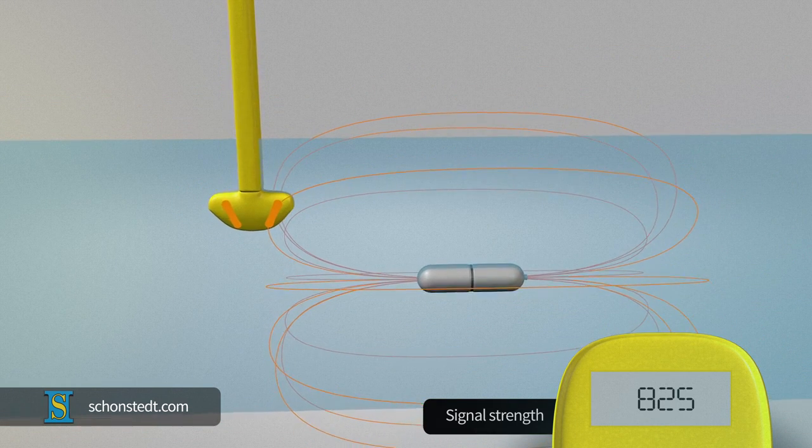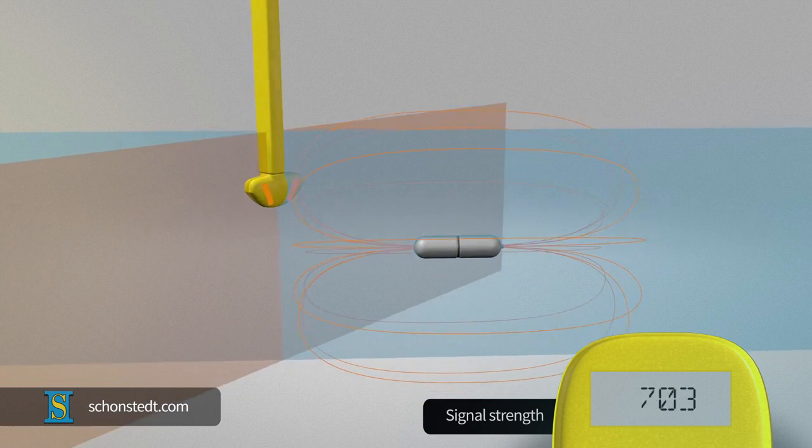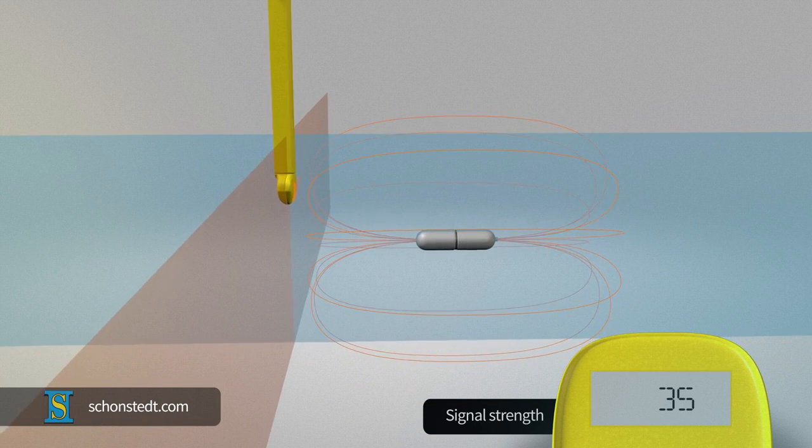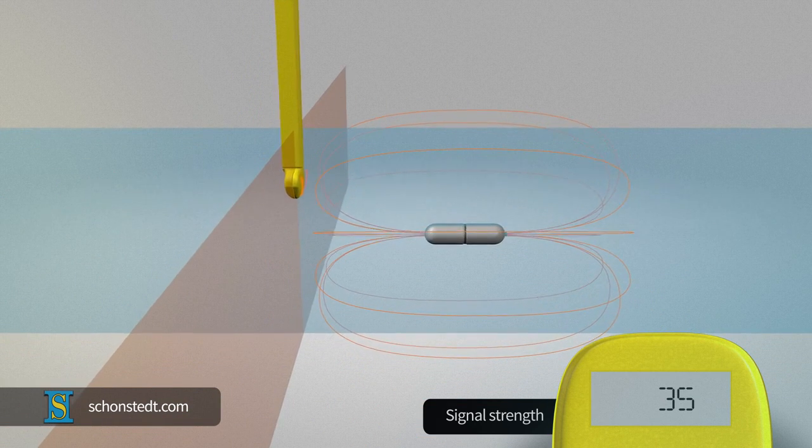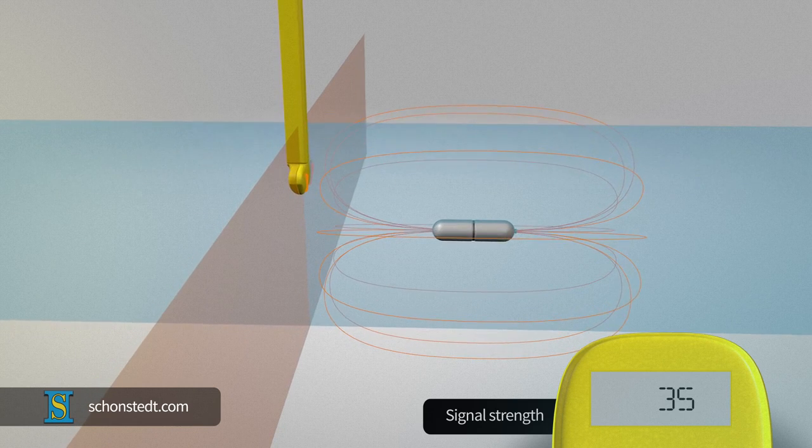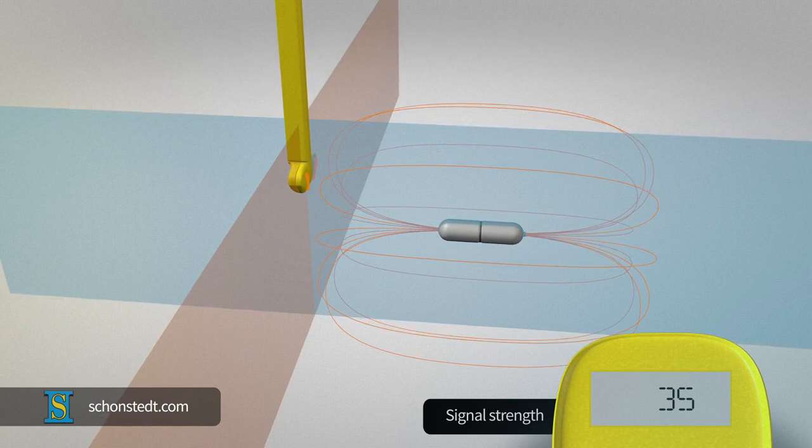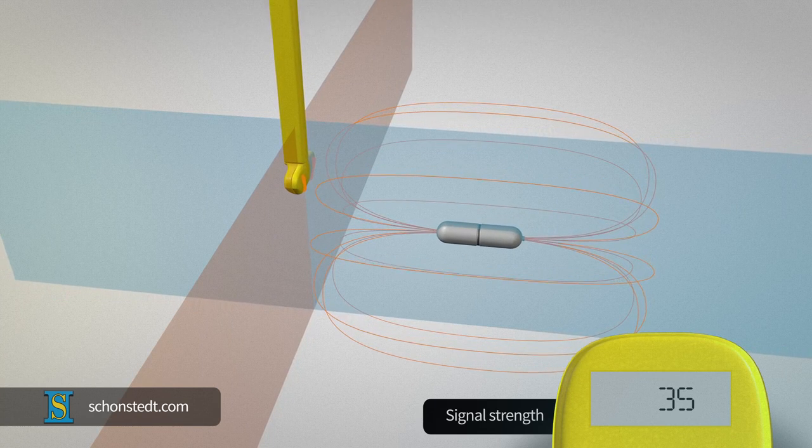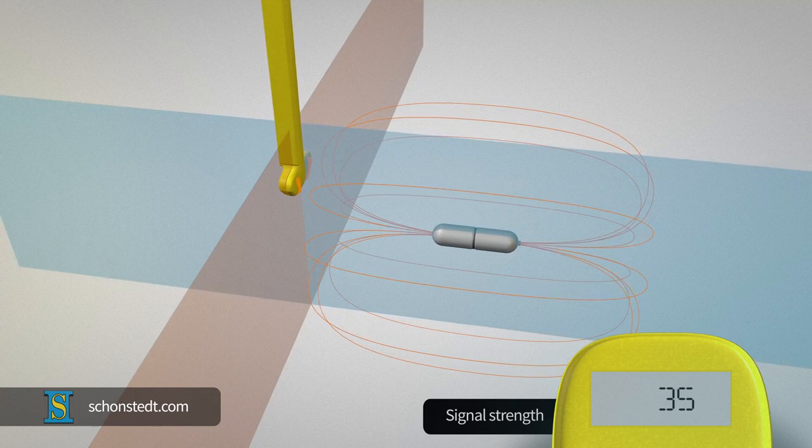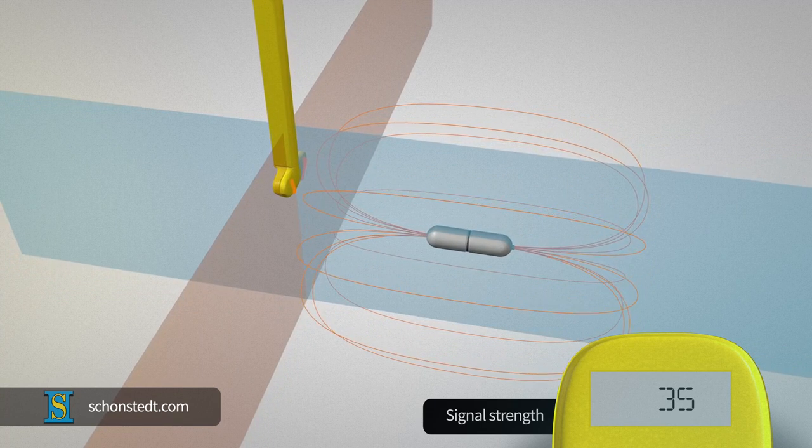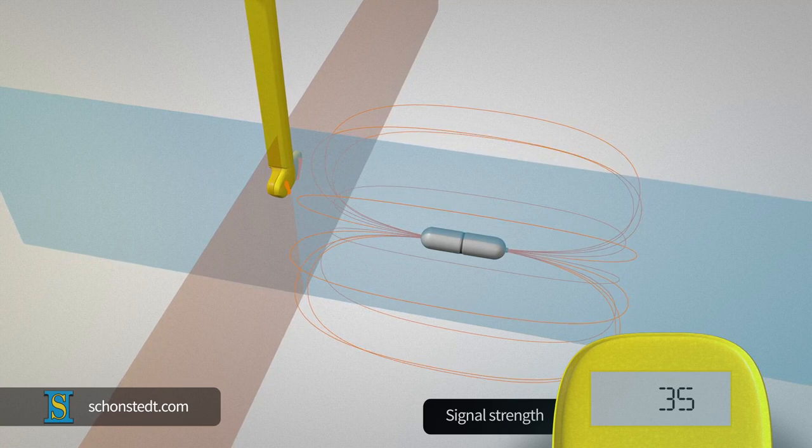By contrast, the signal detected by the sensors is the weakest or null when the axis of the sonde and the axis of the sensors in the receiver are on perpendicular planes. In this case, the field lines of the signal emitted by the sonde are perpendicular to the sensors, generating essentially no signal or a minimal signal.